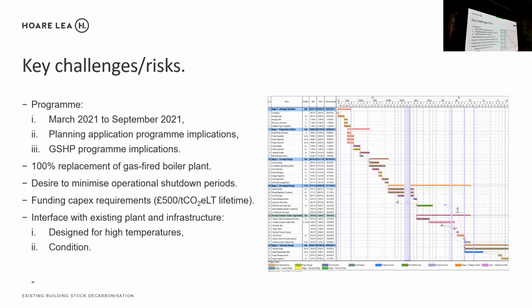Because it was Salix funded, there were CapEx requirements - back on phase 1, it was £500 per tonne saved over the lifetime of the project. And because these were existing buildings, we needed to interface with the existing plant and infrastructure without knowing its condition. Obviously, because they were generally aged installations, they all operated at much higher temperatures than heat pumps can deliver.